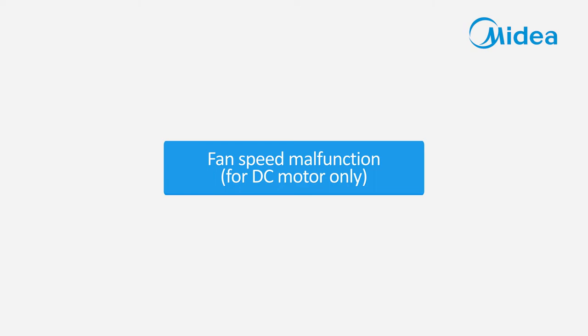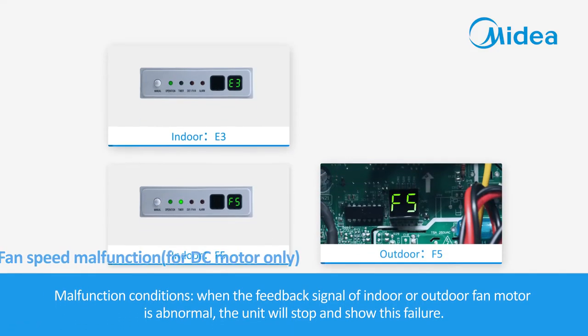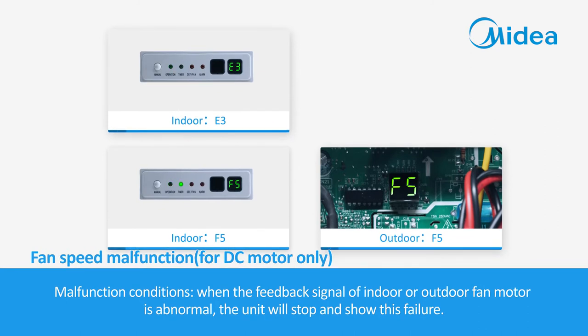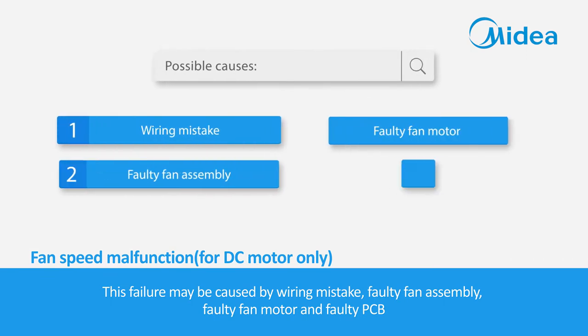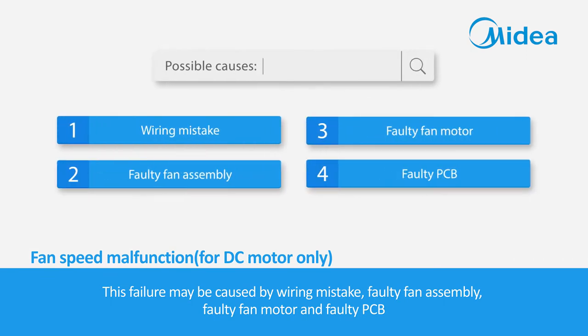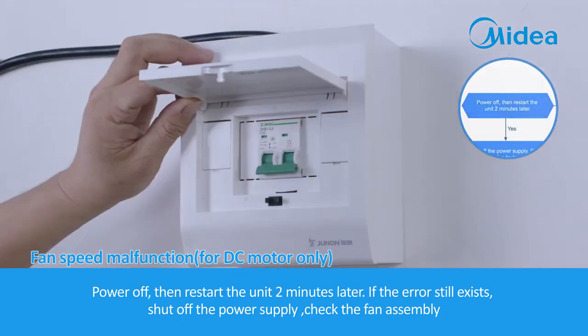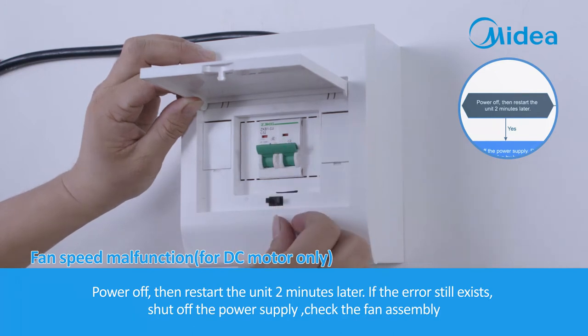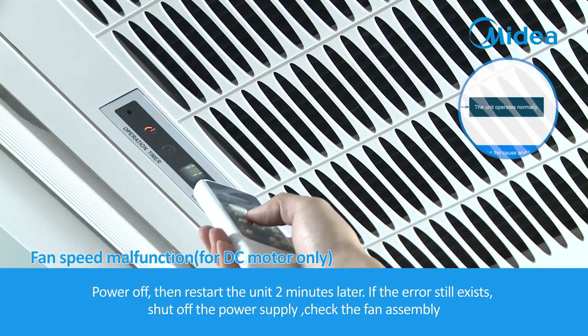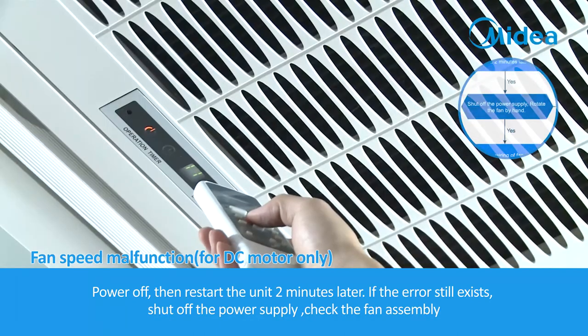Fan speed malfunction (for DC motor only). Malfunction conditions: when the feedback signal of the indoor or outdoor fan motor is abnormal, the unit will stop and show this failure. This failure may be caused by wiring mistake, faulty fan assembly, faulty fan motor, or faulty PCB. Troubleshooting: power off, then restart the unit 2 minutes later. If the error still exists, shut off the power supply and check the fan assembly.